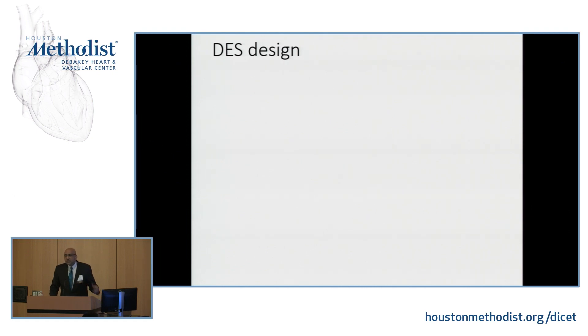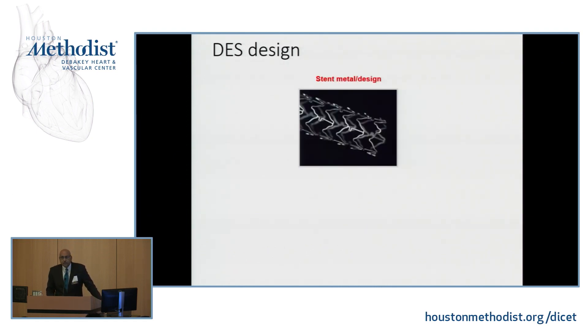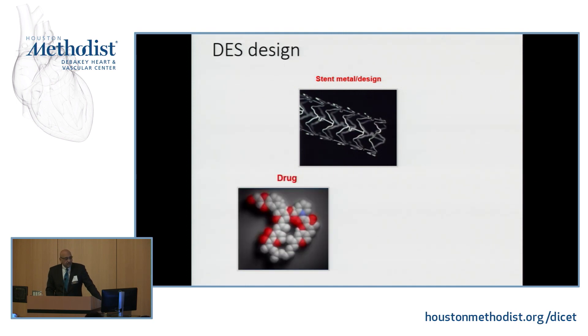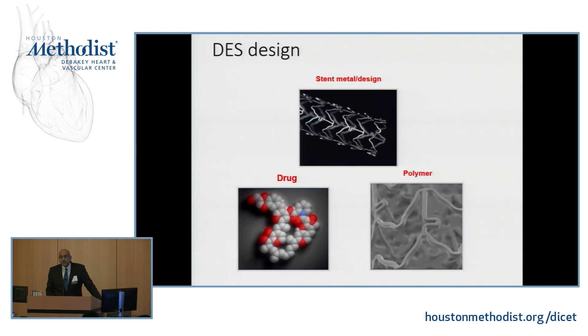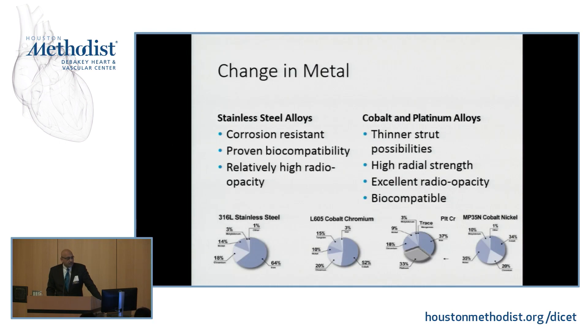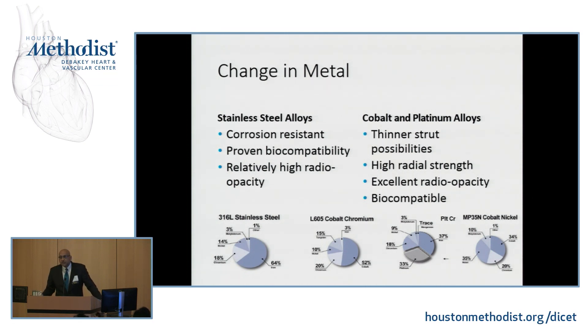What makes drug-eluting stents so significant? There are three parts to any stent: the stent metal or design, the drug, and the polymer coating that carries the drug. The polymer is a plastic layer put on the metal to which the drug molecule attaches. We have changed the metal — earlier bare metal stents used stainless steel, which required very thick struts for drug delivery. We have moved to thinner struts made of cobalt and platinum alloys, which have high radial strength, high radiopacity, and are biocompatible. All new-generation stents have moved away from stainless steel.